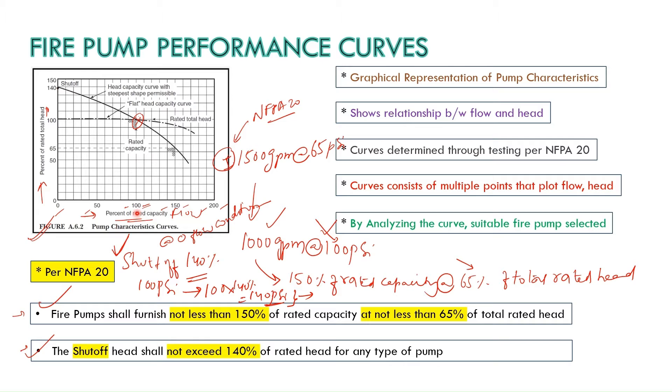So here based on our two points they have shown the curve here. Here you can see the 100% of the rated capacity. For example we have 1000 GPM and it is providing 100% of the total head which is 100 PSI, this will be the point. And second thing is this pump shall produce 150% of the rated capacity. So when you come to here 150% of this one, 150% will be 1500 GPM. So here on y-axis you can see 65% of the total rated head and the shutoff pressure at zero flow condition shall not exceed 140%.